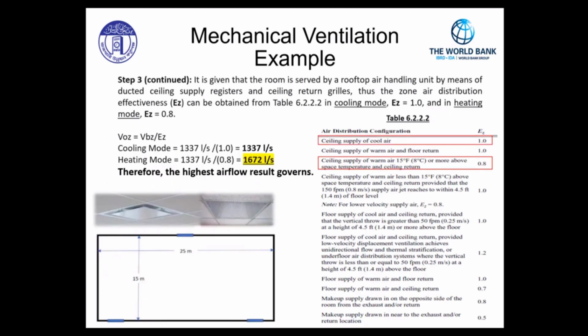Step 3 continued. It's given that the room is served by a rooftop air handling unit. Remember, this is a single zone system by means of ducted ceiling supply registers and ceiling return grills. Thus, the zone air distribution effectiveness, E sub Z, can be obtained from table 6.2.2.2. In cooling mode, E sub Z is selected as 1.0. Noting the table below, we do have ceiling supply of cool air. We will take that particular value and use it in the cooling portion of the equation.